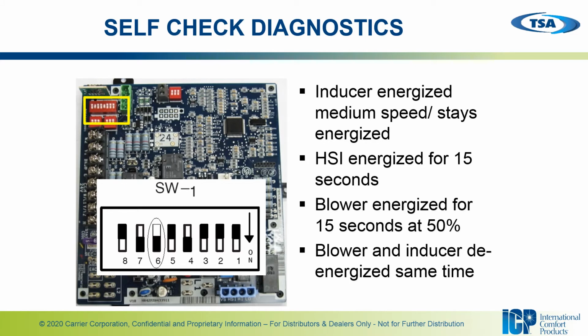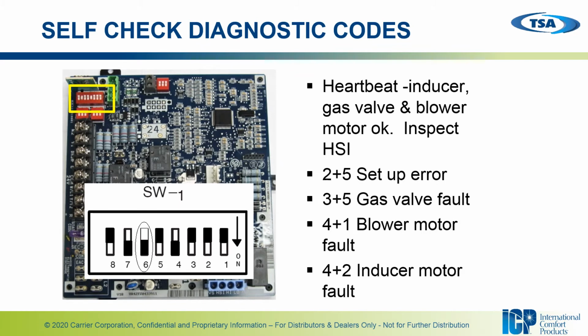Once you enter the test mode, the process will proceed as follows. Your inducer is going to energize at medium speed, and it will stay energized through almost the entire process. Then your hot surface igniter is going to energize for 15 seconds, followed by your blower motor being energized 15 seconds after that. Your blower and inducer are going to de-energize at the same time at the end of the cycle. Once the cycle's complete, a heartbeat on the LEDs is going to indicate that the inducer, the gas valve, and the blower motor have all checked out okay. However, the hot surface igniter must be checked by a visual inspection by the technician.